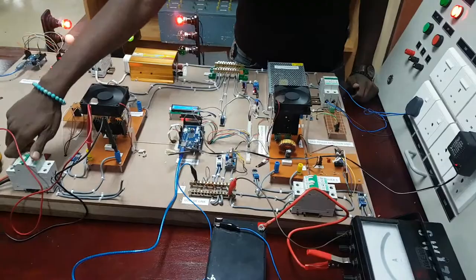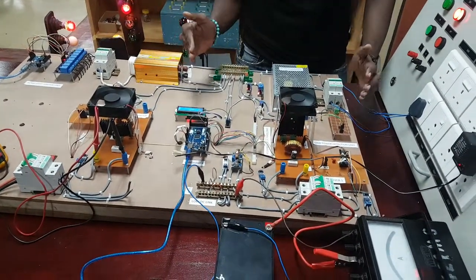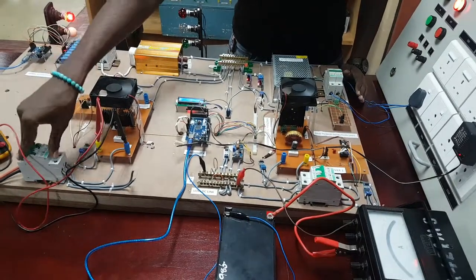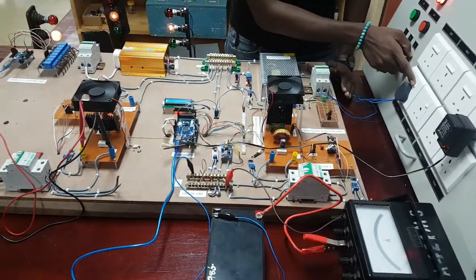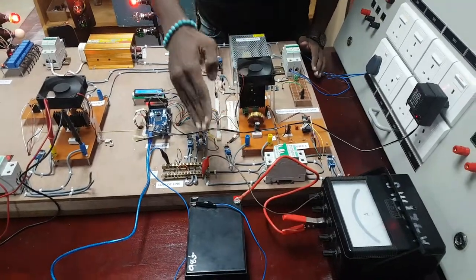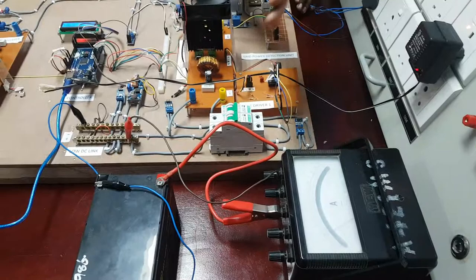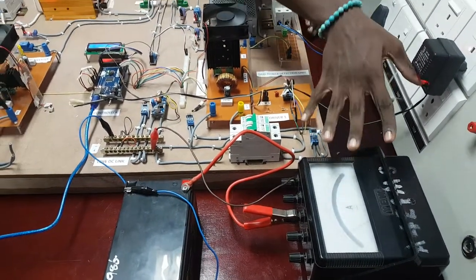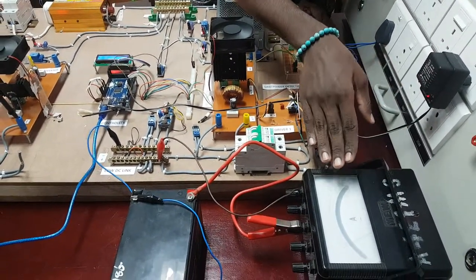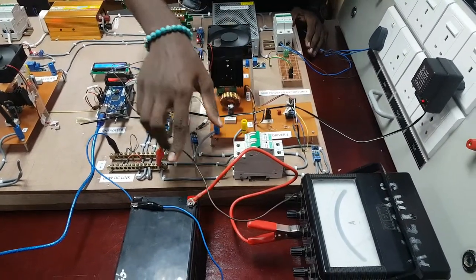If we turn the battery back on and then turn solar off, the load is now being supplied by the battery. When the grid supply comes back on, the battery goes into charging mode and there is a charging current to the battery. This ammeter is connected to detect the current going into the battery.